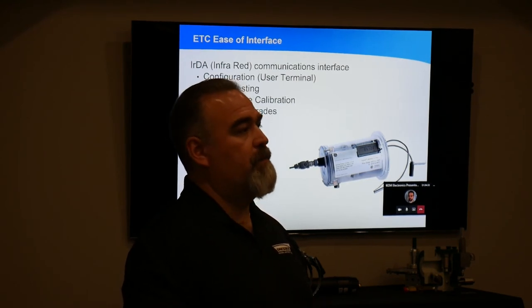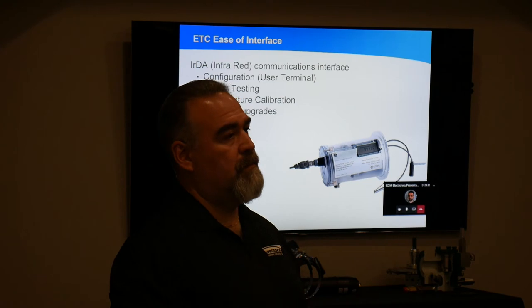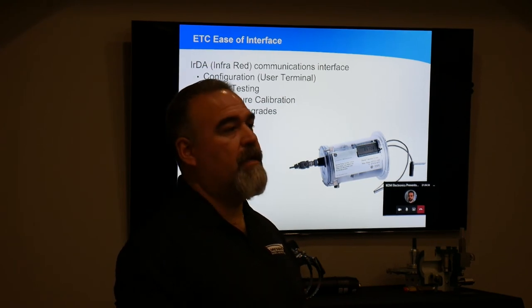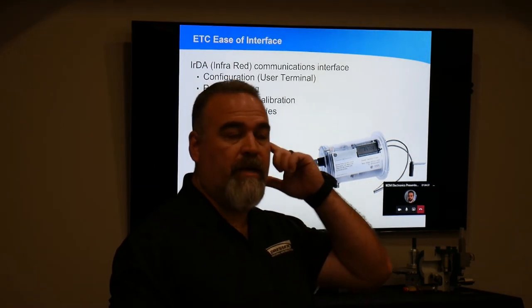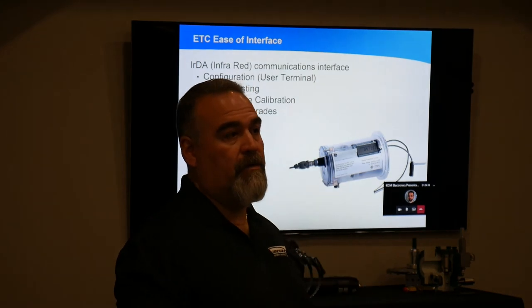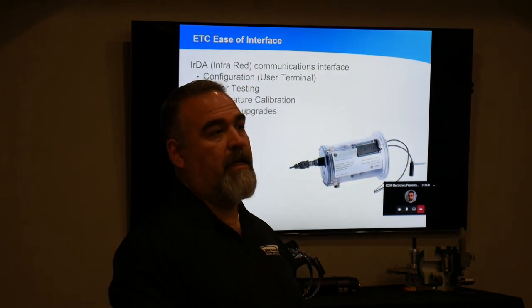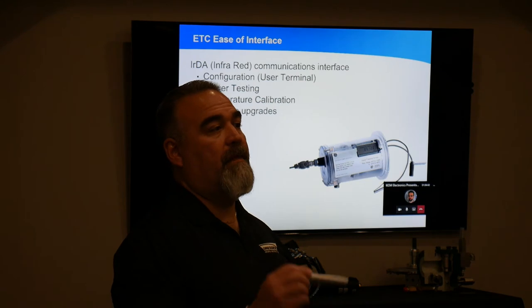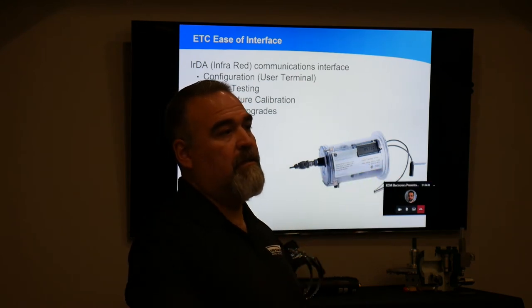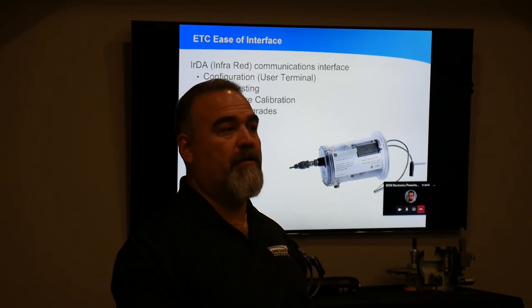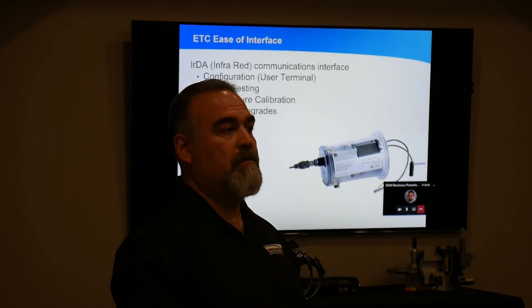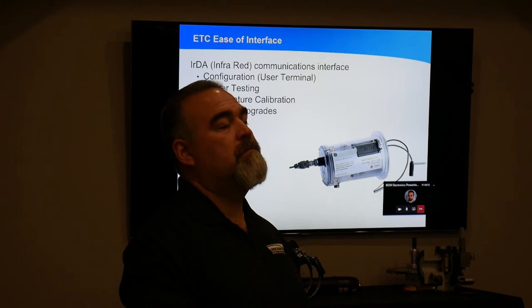It's a single point calibration, yes. You go into the software to do that. You'll go into the meterware, do the single point calibration, see what the reading is, then refer it to the reference and make the changes there if needed. It's a very large customer, and that's one of their first questions - if anything has a temperature probe for electronic correction, can we do an ice bath calibration on it?